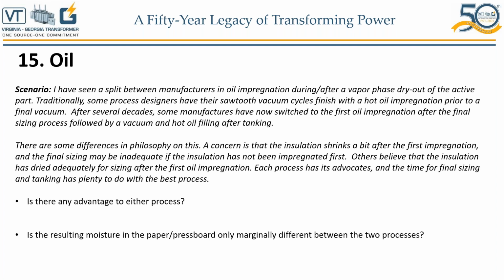Oil. I have seen split between manufacturers in oil impregnation during and after a vapor phase dry out. Traditionally, this is good. I'm going to summarize here. Pretty much what the question is talking about here is when we dry the transformers in vapor phase, during and maybe after the vapor phase process, we actually do oil soaking, or as it says here, hot oil impregnation prior to final vacuum.